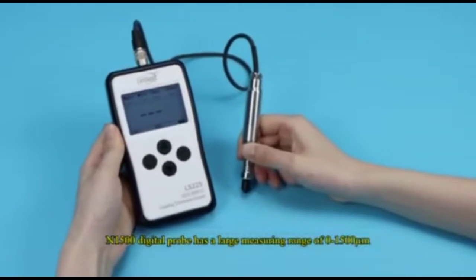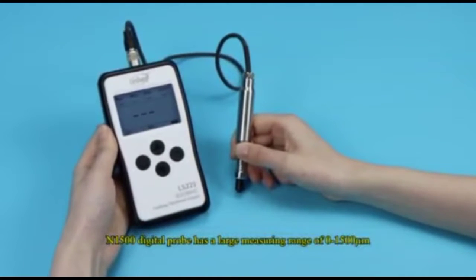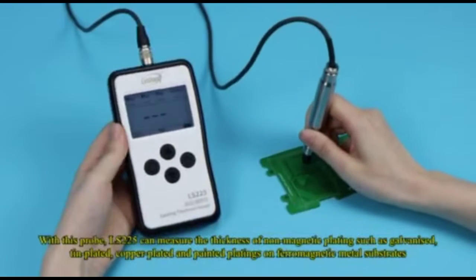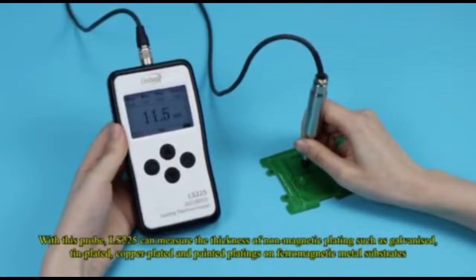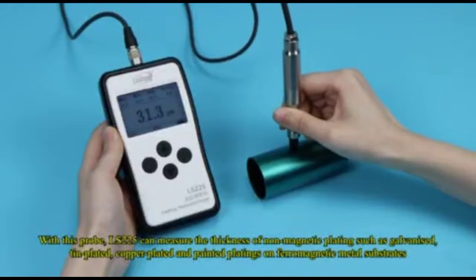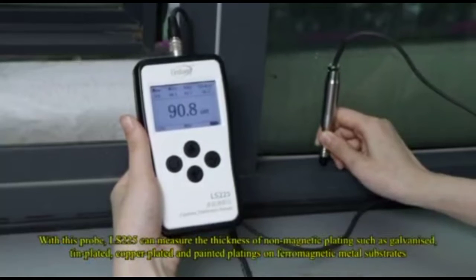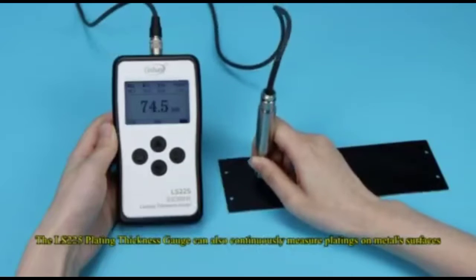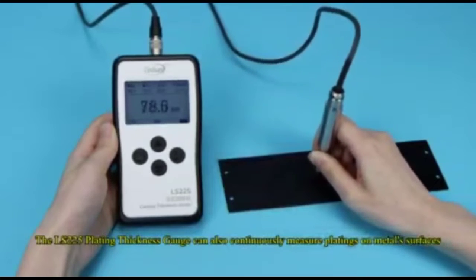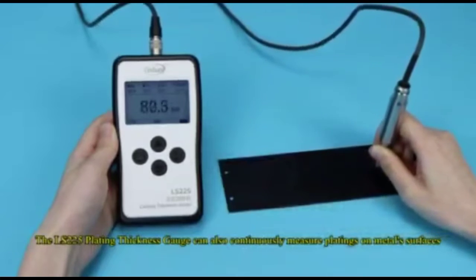N1500 digital probe has a large measuring range of 0 to 1500 micrometers. With this probe, LS-225 can measure the thickness of non-magnetic platings such as galvanized, tin-plated, copper-plated and painted platings on ferromagnetic metal substrates. The LS-225 plating thickness gauge can also continuously measure platings on metal surfaces.